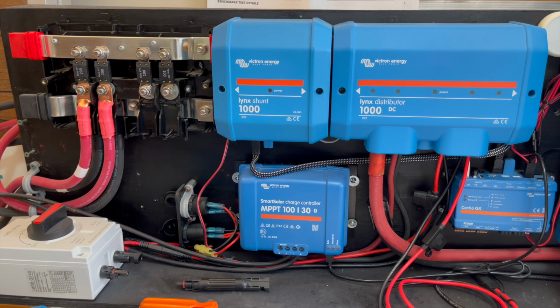If it's not the same, try moving your negative to the opposite end of your bus bar. So your positive will be on the top of your server rack, and your negative will be at the bottom. I'll point out the reasons why. If that doesn't work, or it still needs improvement, check your cabling. Be sure you're using the same quality and size of cabling, and also your connectors. I've seen people use different size connectors, one big, one small. This all adds up. So in the way you connect things, you need to check that to be sure. Double check that everything's tied down.